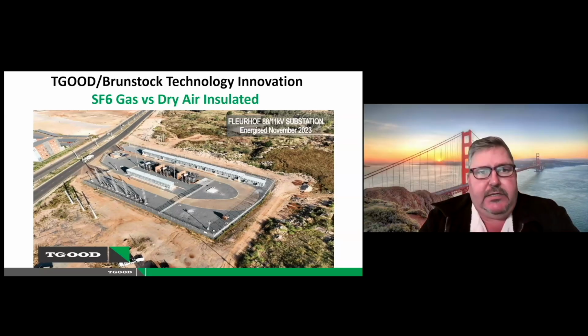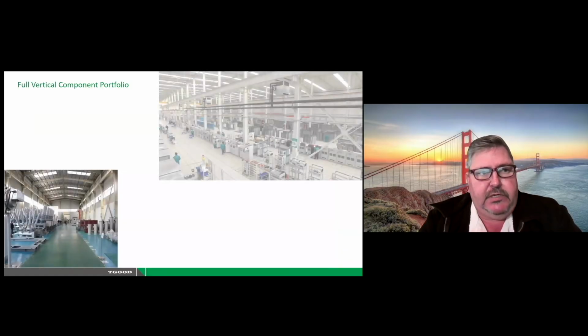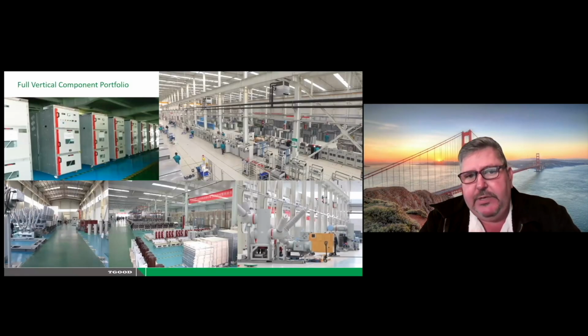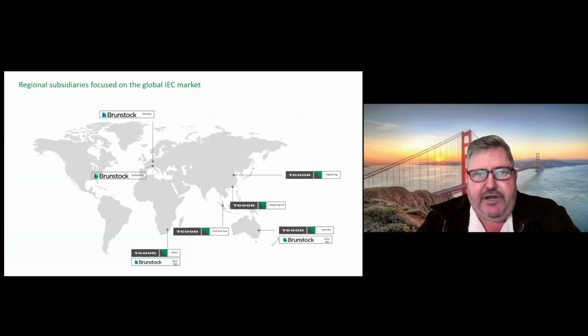TGOOD just wants to point out the difference between SF6 gas and dry air insulated switchgear. As you know, we're in the renewable energy market space where everything is green. So TGOOD's portfolio is that we can offer, as an OEM, original equipment manufacturer, a full range of products contributing to your solutions, from 3.3 kV up to 132 kV. We've got different manufacturing facilities. Our SF6-free range is manufactured in Germany and Switzerland, and our other products are in China, with a head office in Hong Kong, and we also have branches across the globe.